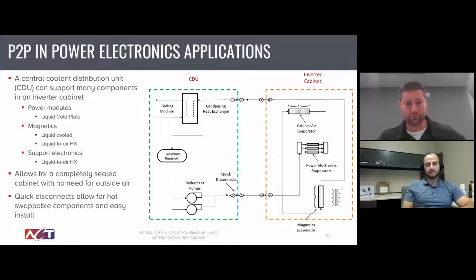Just on the dielectric portion of the loops, which is really what's enabling this: if we had a non-dielectric or conductive fluid, we wouldn't be able to send the fluid through all the individual components in, say, an inverter cabinet in series or parallel like this, because we'd be connecting them electrically. The fact that the system is dielectric and can service multiple different types of evaporators makes it really attractive for applications like this, and we found wide use of this technology in the power electronics industry.